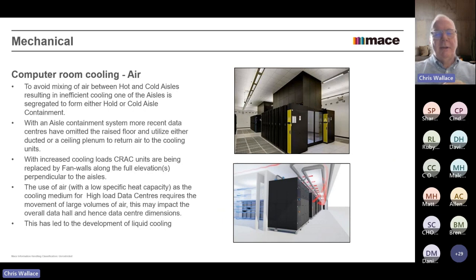So the problem with all this becomes when you're getting to high cabinet loads, and I'm talking anything more than about 20 kilowatts a cabinet, you're going to end up moving a huge volume of air. I once did a presentation to DCD in Singapore, and I had a slide showing string vests, and people were like, why have you got that slide up? I said, well, string vests work. They keep you warm in winter back in the UK because they've got an air pocket in them, and they keep you cool in summer because they've got an air pocket in them.